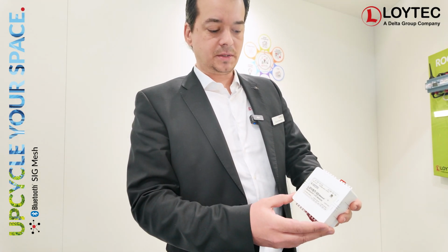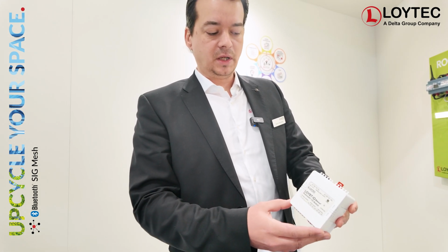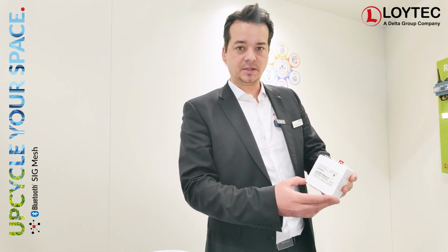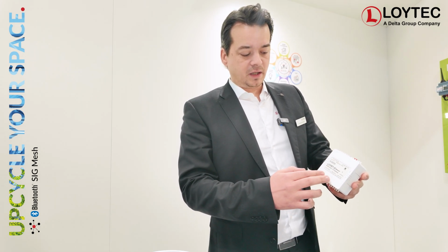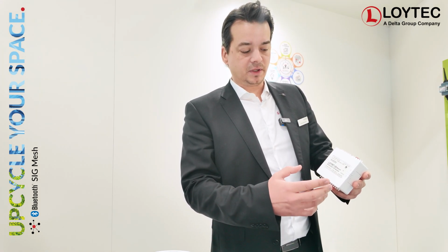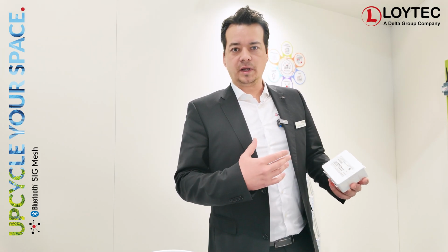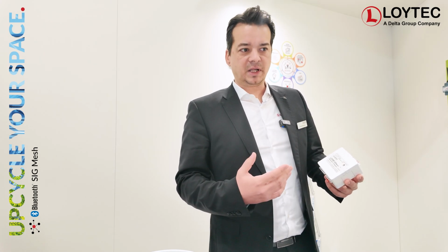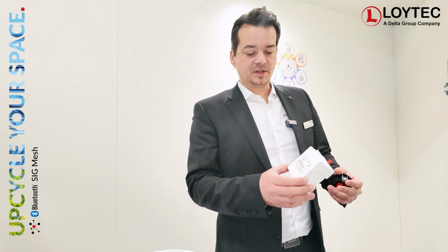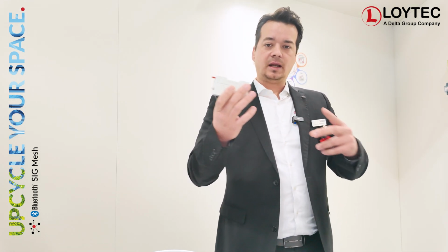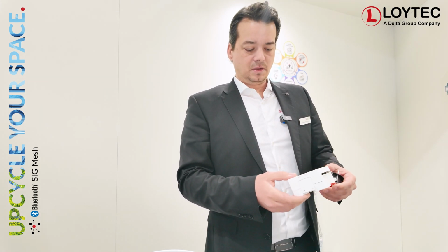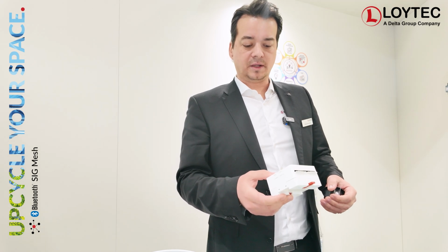We also provide our new LOYBT I/O modules, which is a Bluetooth I/O module, especially designed for any kind of HVAC applications. We have relays on board, we have universal I/Os, we have triacs, so you can control any kind of HVAC application like heating, cooling, ceiling, like VAV applications. You can connect window contacts, dew point sensors to it. And this is just installed in the ceiling, communicating via Bluetooth to the controller, and then just switching on and off and providing the sensor data that are connected to it.